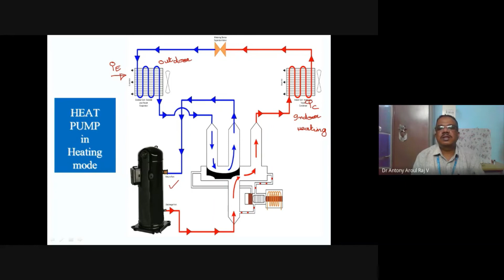The same heat pump can be used in the cooling mode. So this will remain as indoor and this will remain as outdoor only. If you want to work the same heat pump in the cooling mode, what you have to do? Indoor should become evaporator and outdoor should become condenser. That means the hot gas from the compressor should go outside. So that is outdoor. That is the system we will be seeing next.